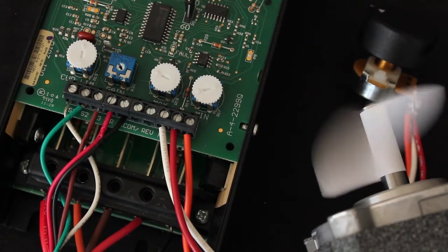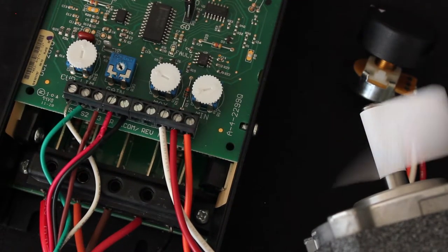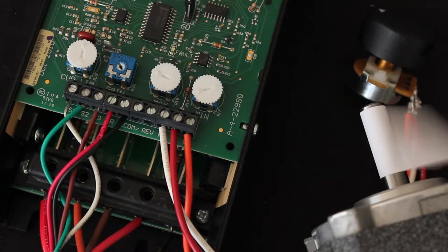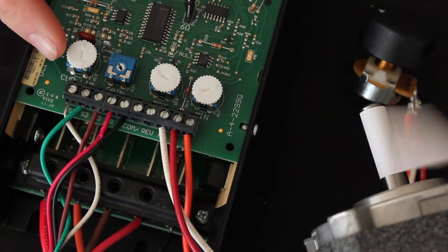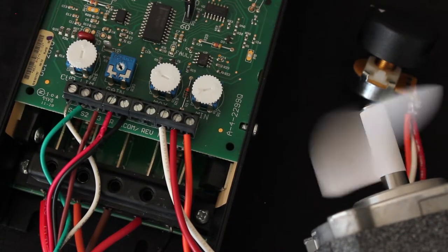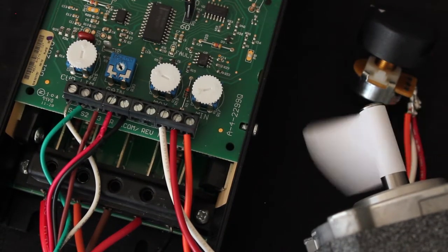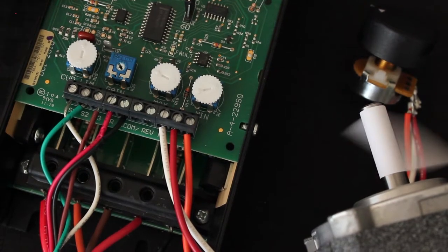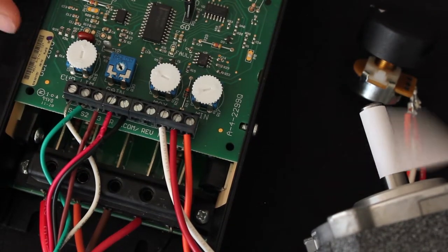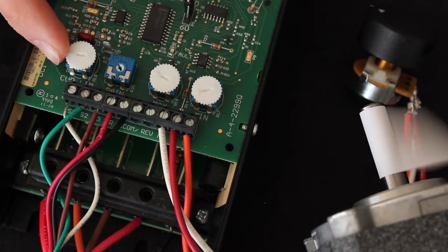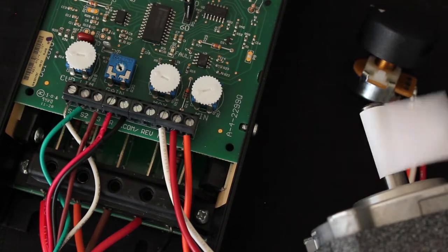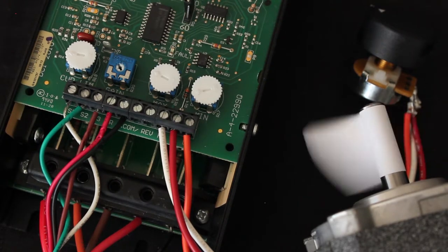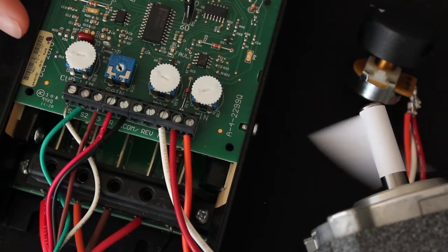The current limit is adjustable from 0 to 200 percent. When it is facing forward, it is set to 100 percent or 20 amps. When rotated counterclockwise 90 degrees, the current limit would be set to 10 amps.